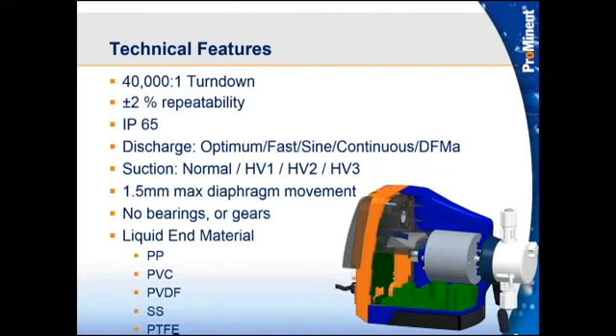Consistent discharge, suction stroke. Continuous would be if I'm running the frequency down really low, I can have it do continuous discharges. Like I said, the pump can theoretically do 1 continuous discharge stroke an hour. Okay. With that being said, you'll see that the diaphragm movement is 1.5 millimeters. You'll need to keep that in mind. That's somewhere around a 1/16 of an inch. So we're not moving that diaphragm very much. That gives us an advantage that will prevent a lot of wear of the diaphragm. Okay. But at the same time, to move all that fluid, we're only moving a total of a 1/16 of an inch on our suction or discharge stroke.